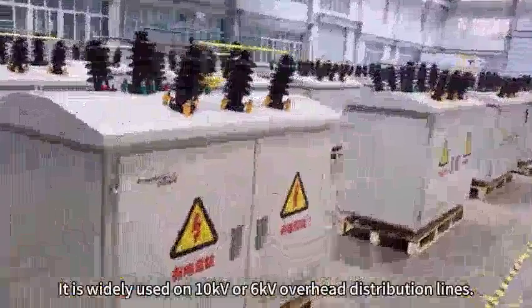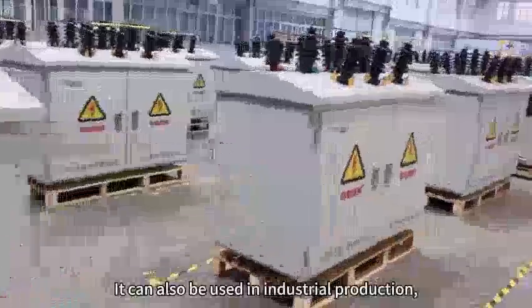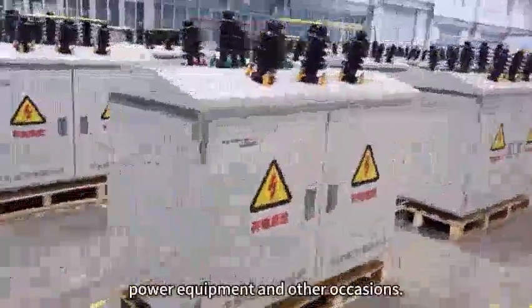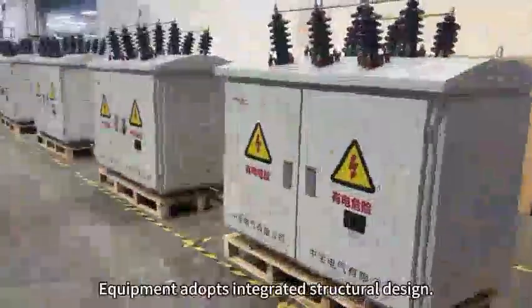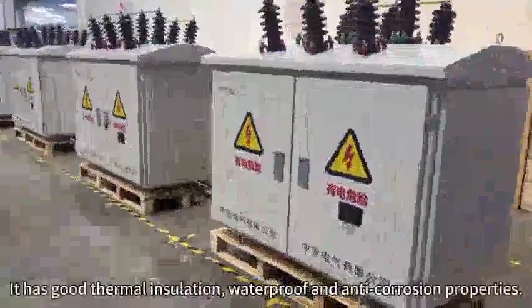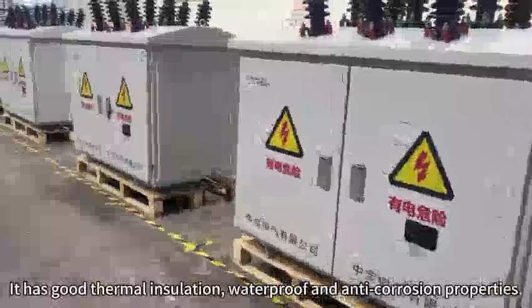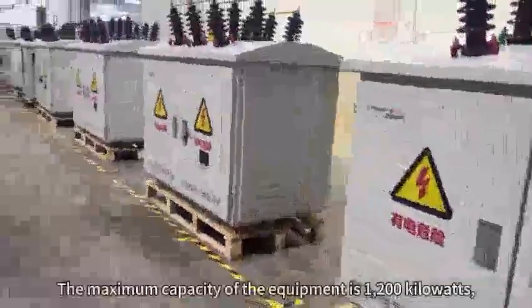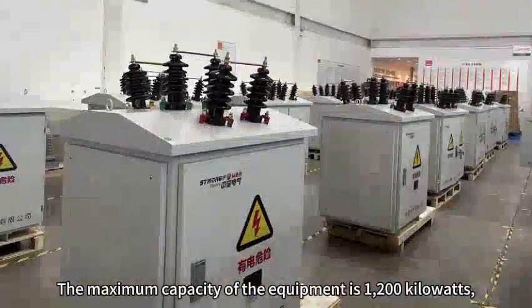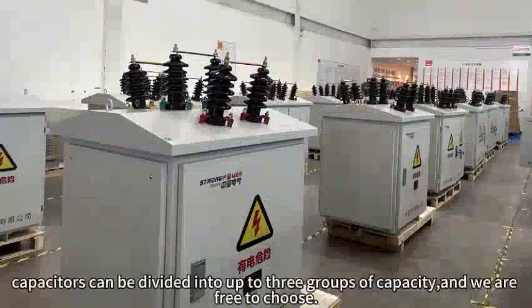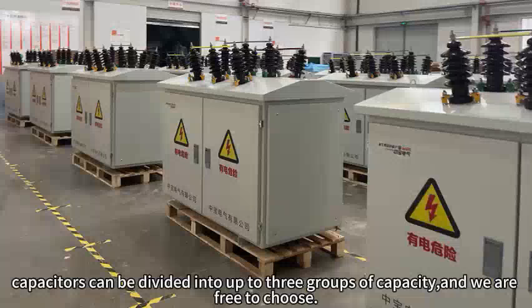It is widely used on 10 kV or 6 kV overhead distribution lines. It can also be used in industrial production, power equipment and other occasions. The equipment adopts an integrated structural design. It has good thermal insulation, waterproof and anti-corrosion properties. The maximum capacity of the equipment is 1,200 kilowatts. Capacitors can be divided into up to 3 groups of capacity, and we are free to choose.